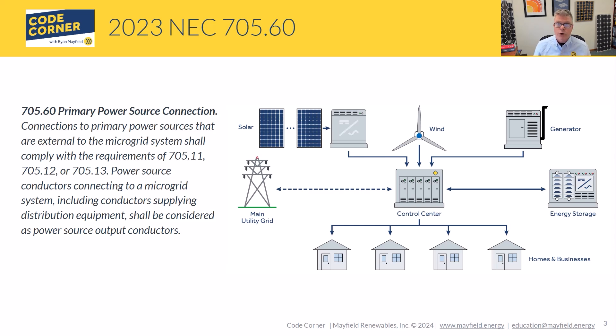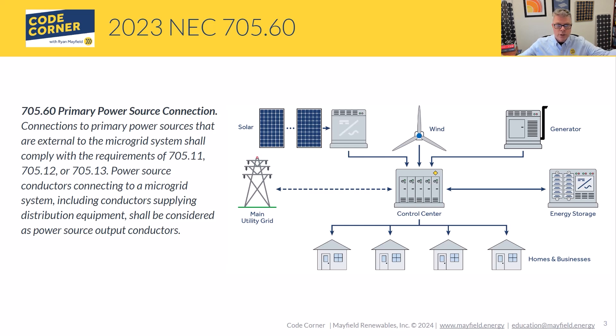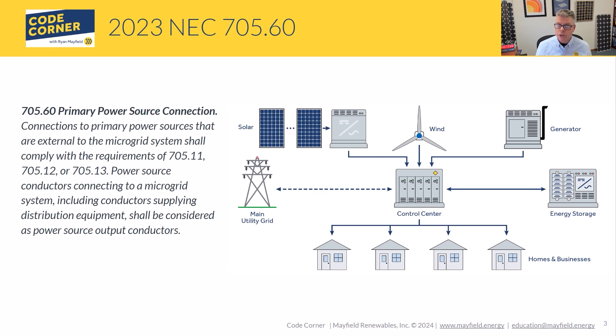Those rules apply to interconnecting our microgrid system just as they would for a straight PV system with utility. The code also states that power source conductors connecting to a microgrid system, including the conductors supplying distribution equipment, shall be considered as power source output conductors. We're going to look at the rules in 705 to size those, protect those, and address rules around loss of power — applying Article 705 across the board for those sets of conductors.